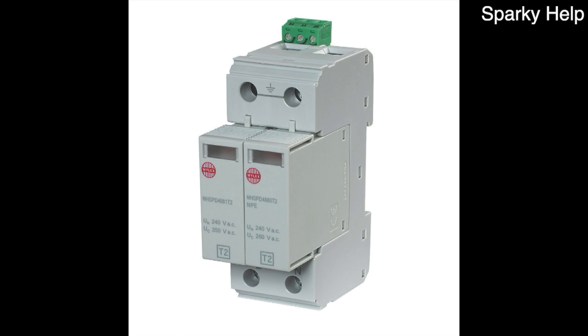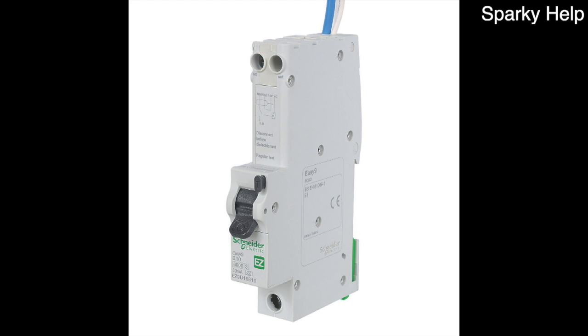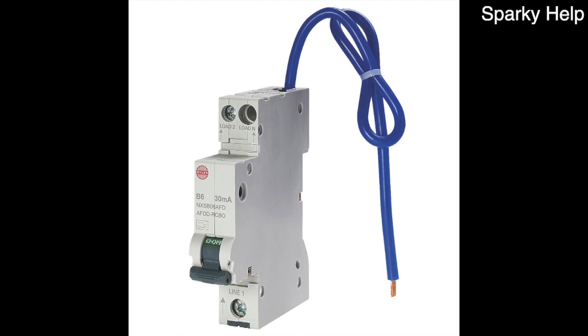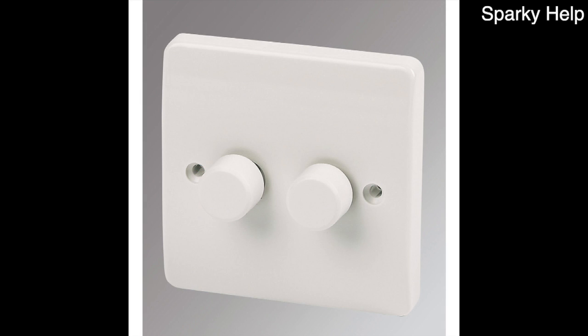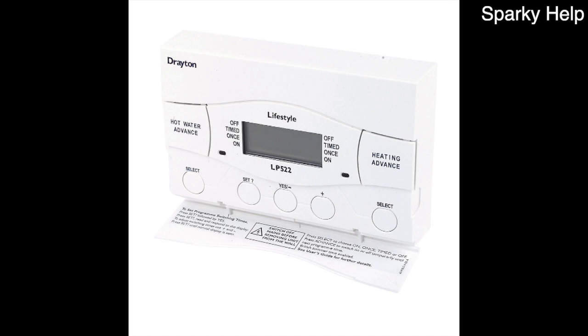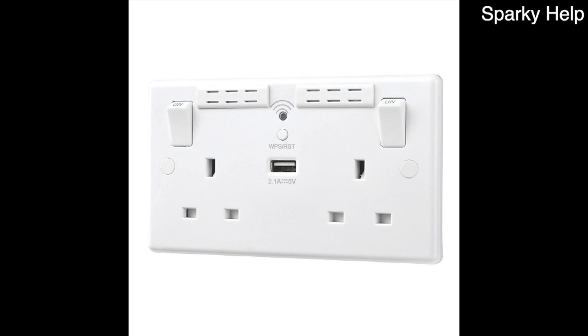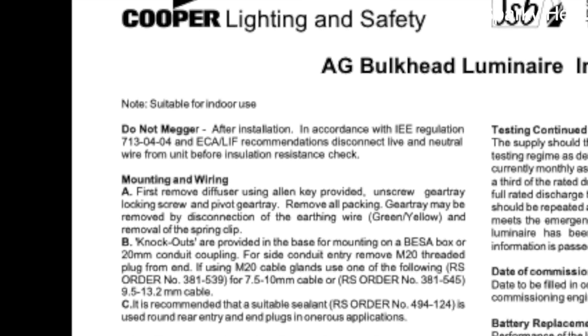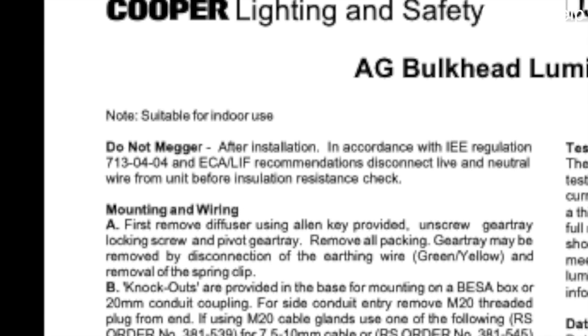So what sort of things could we have connected in? Well, surge protective devices, which are going to become more and more common if you aren't already seeing them now, definitely cannot be tested and therefore may need to be disconnected from the circuit. RCBOs, obviously been around for years, may not be able to be tested and you may damage them. New to the market, arc fault detection, and here we have a Wylex, and this one has all three in one, so it's an arc fault detection, RCBO and circuit breaker. Dimmer circuits and anything with dimmer switches needs to be removed, as do time clocks and also USB sockets. That bit of paper that you threw away when you were installing that equipment, you may need to read it, because it may well say "do not Megger".